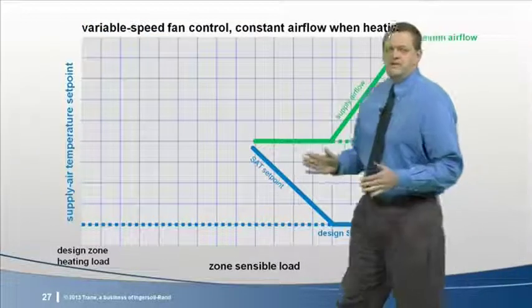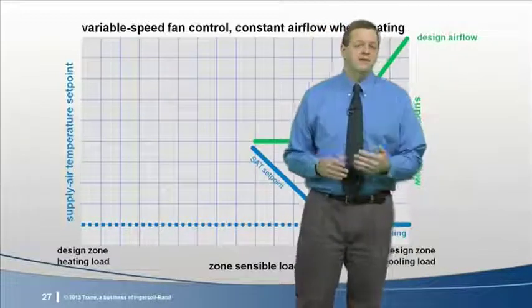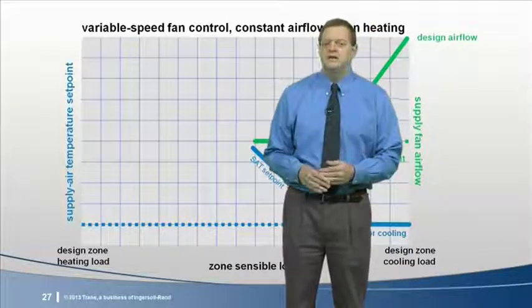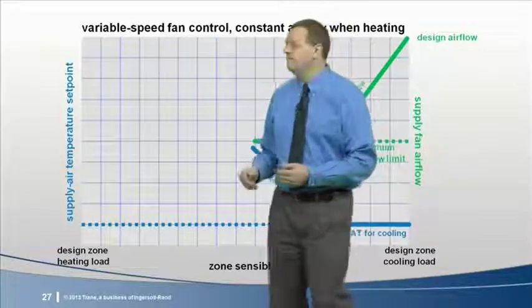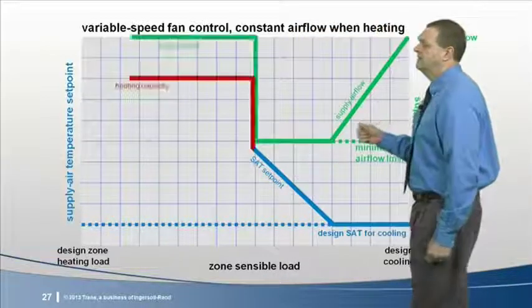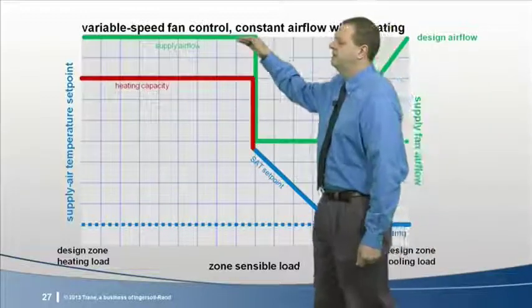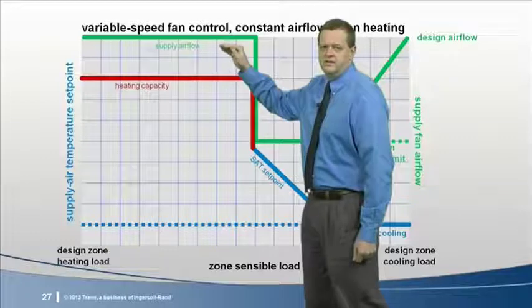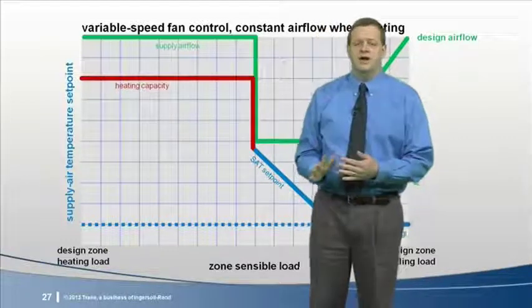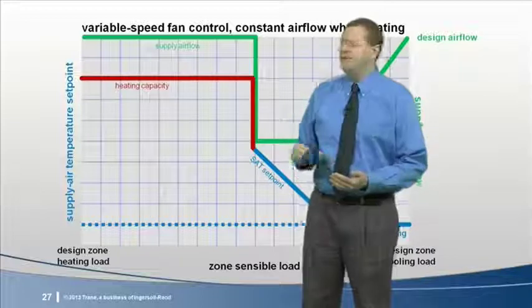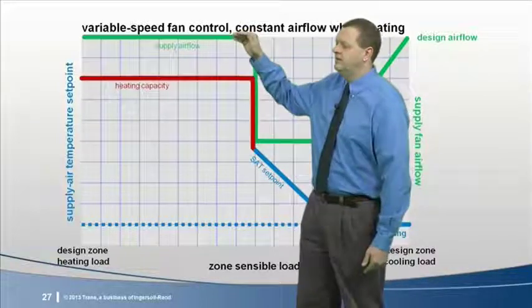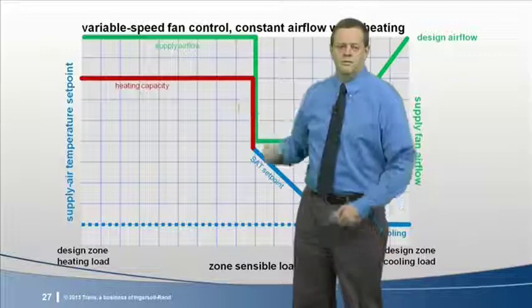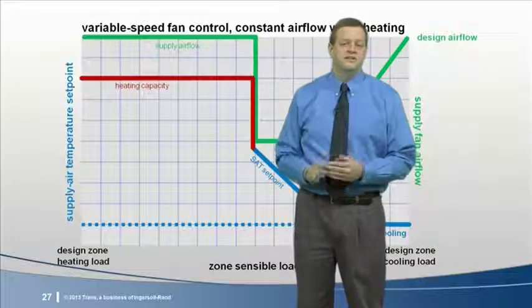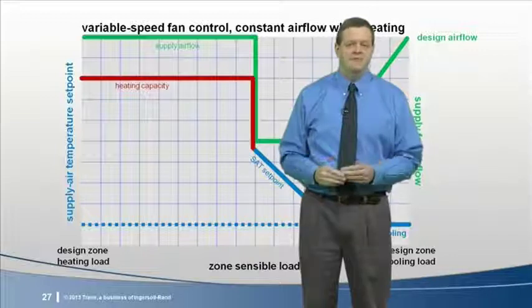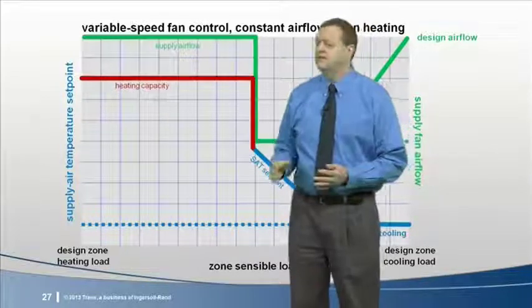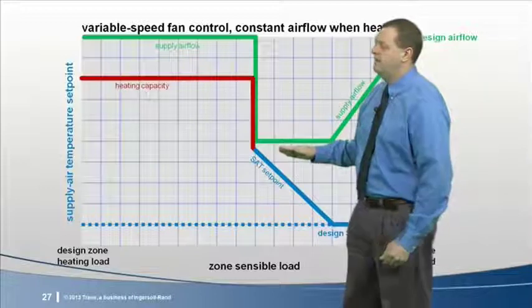Now, for some types of equipment, the type of heater available may not be able to accommodate variable airflow. In that case, the control sequence may vary airflow during cooling, but then increase to some constant airflow whenever the heater is activated. That is, if the zone temperature drops below its heating set point, the fan ramps up to full speed, and the heater is cycled or staged to warm up the zone. Once the zone temperature is raised back up to that dead band between heating and cooling set points, the heater turns off and the fan again backs down to minimum speed.